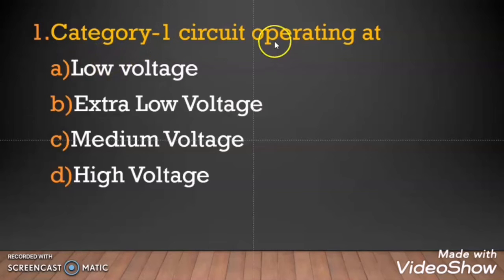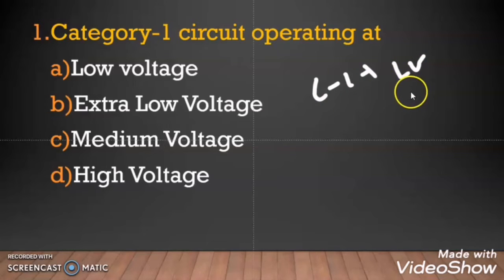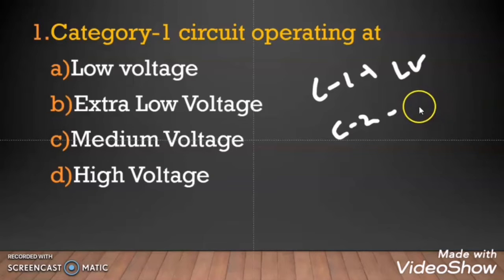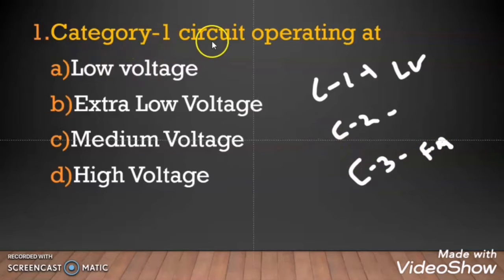Question 1: Category 1 circuit operates at which voltage? Options are low voltage, extra low voltage, medium voltage, or high voltage. As per ADDC regulation, there are three types of circuits. Category 1 is for low voltage system. Category 2 is for communications like telephone system wires and CCTV system wires. Category 3 circuits include fire alarm wire and central battery system wire. So as per the question, category 1 circuit operating at low voltage is the right answer.